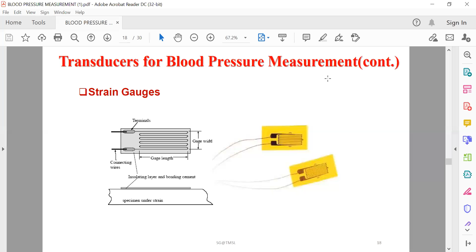Next, the transducer for blood pressure measurement, which is basically the LVDT, linear variable differential transformer. This transducer looks similar to the unbonded strain gauge type, with respect to the plastic dome used for visibility, the two pressure fittings for attachment to the catheter and for flushing, and the cable coming out of the bottom. They are similar.